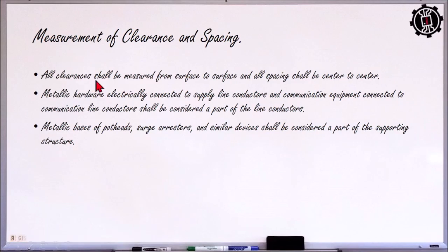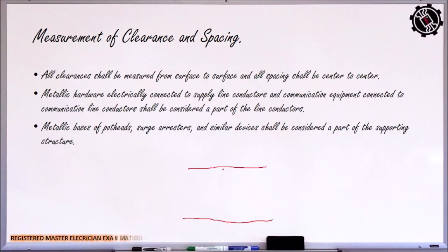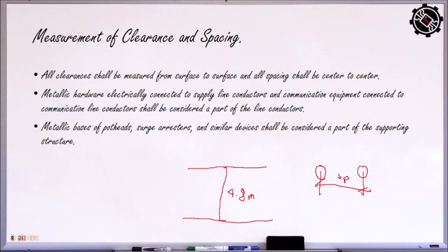So all clearances shall be measured from surface to surface. Ibig sabihin yan, if for instance, so ito yung surface ng road mo, ito yung wire. So yung surface ng wire dito, tapos yung surface ng road, so yan yung ibig sabihin ng clearance. That is 4.8 meters, no? Yung kanina, if that is heavy traffic o may daraan na truck. So surface to surface. When it comes to spacing naman, so spacing is usually applicable to conductors to conductors. So kunyari may dalawa kang conductors. So the measurement for spacing is center to center. So center ng conductors. So that is the spacing. Ito naman is the clearance.